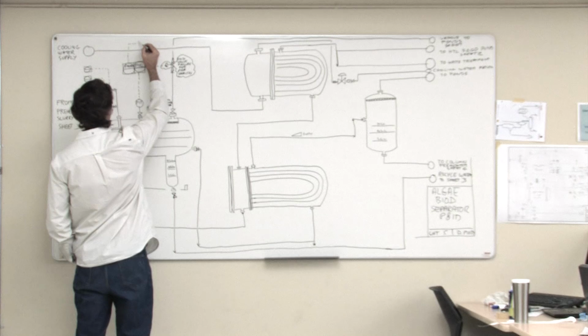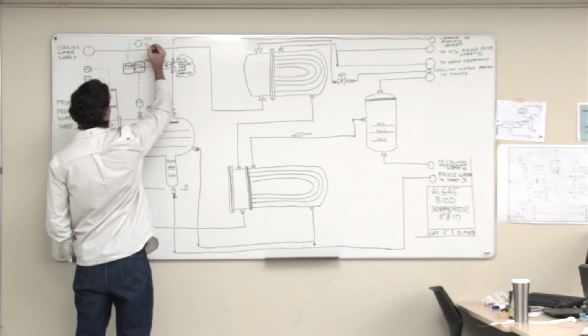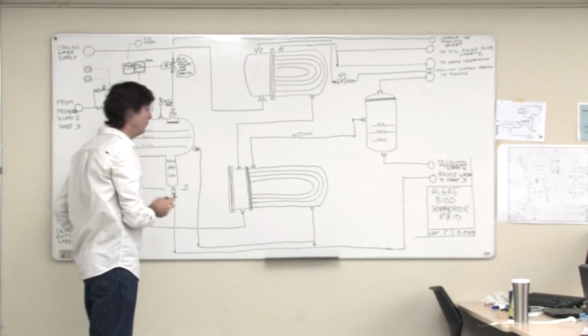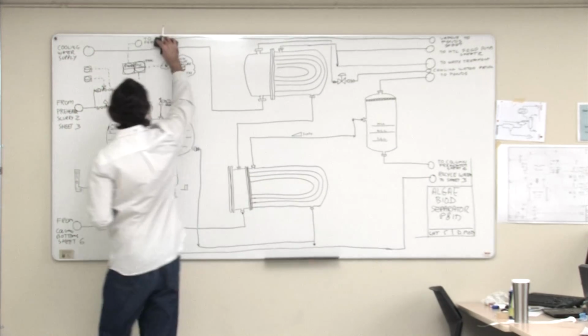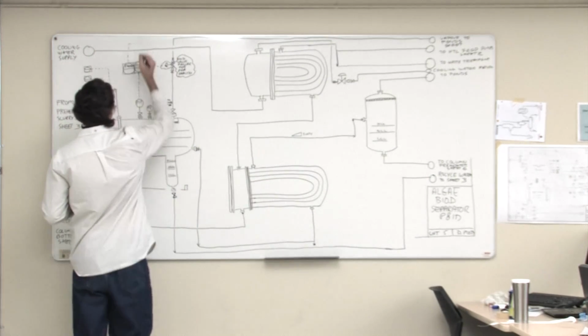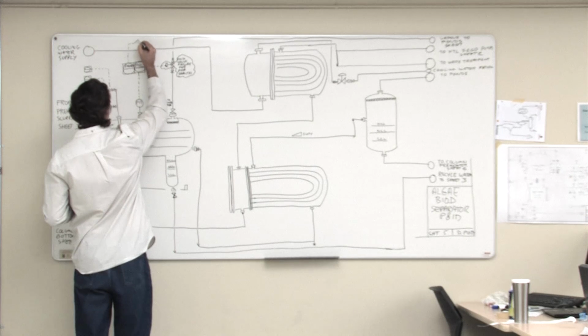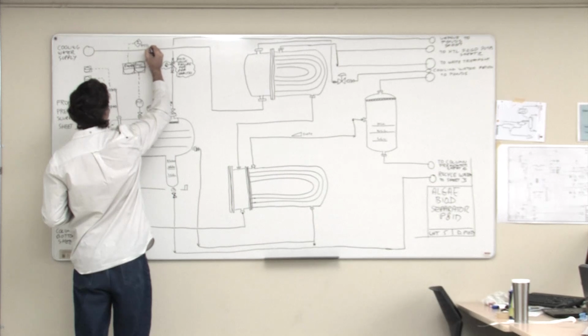I'm obviously never going to fit that in there, so we would say 'to feed pump interlock, two feed pumps.' Actually, the other way to do it would be to just show it right as an interlock symbol - that might not be a bad way to do it. So, and that actually is fairly... show it as an interlock like that and call it the feed pump shutdown.